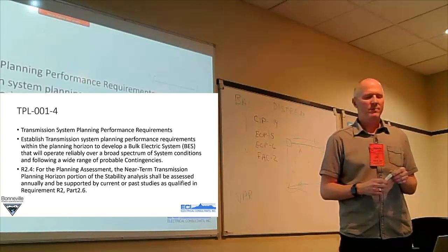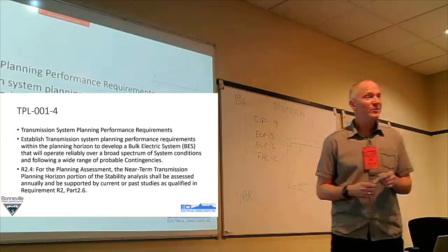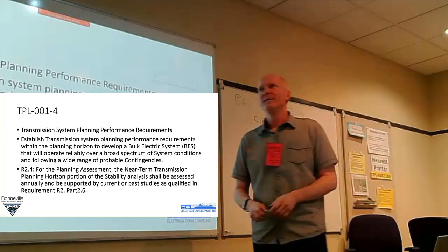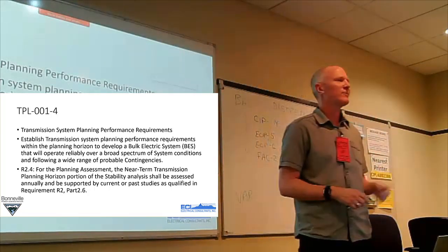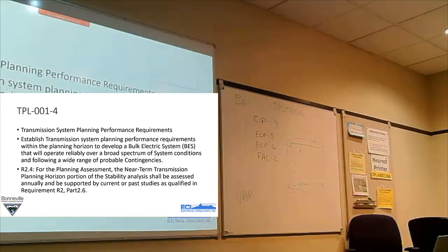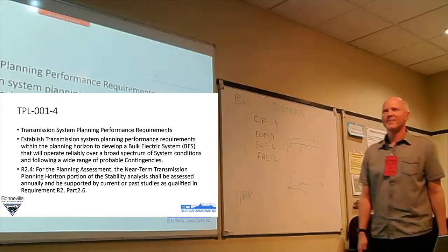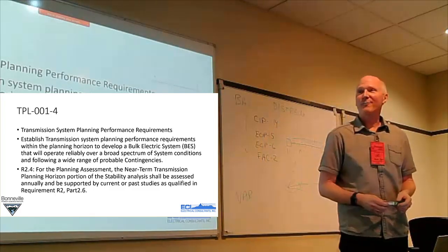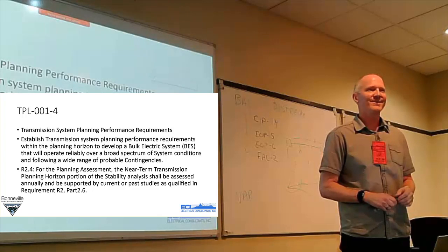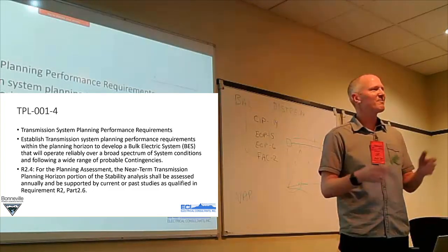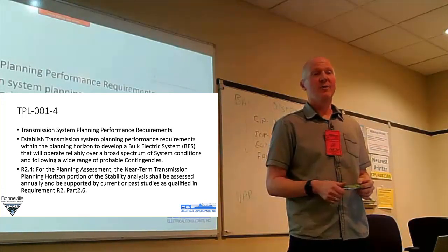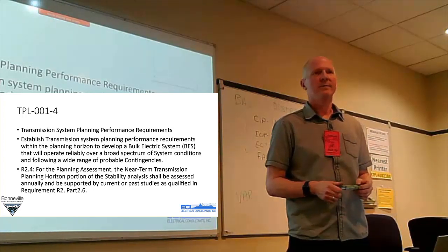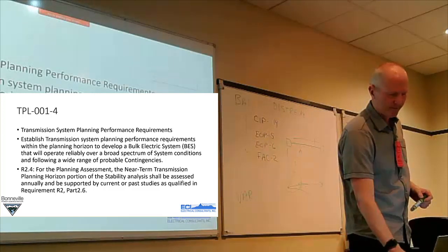Some customers have been doing it. I don't completely understand why. The super good news for WECC, so feel better about yourselves, is the MISO case, 88,000 buses. Oh my gosh, it takes so long to solve just a single time. Power flow solves, solves, MISO, solve, solve, it's slow. It's horrible. Stability is not so bad because they all use ZIP models for loads. The power flow was the issue. Gosh, that's a horrible case. Stability is about the same. Really? It's forever long, and it's got like 10 islands in it. It's just a nightmare. By comparison, full topology cases take 2 to 5 seconds to solve, on a good day. But they're getting consolidated. They're similar to a WECC case in the solution.